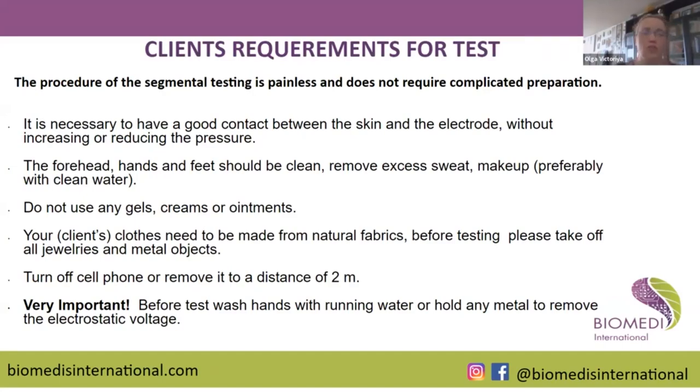Do not use any gels, creams, or ointments instead of water to make the connection better. That is not good. The test results are not going to show you the true picture.